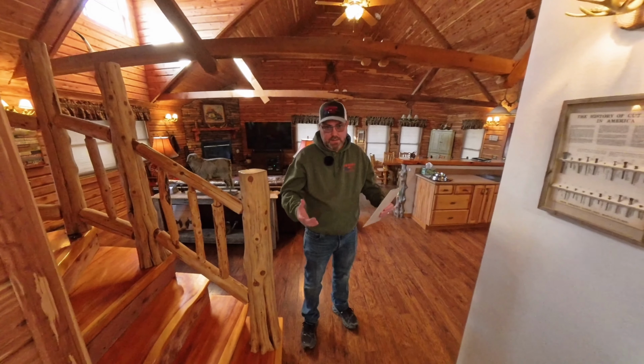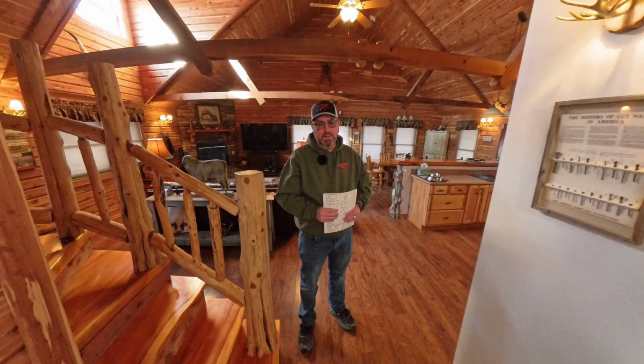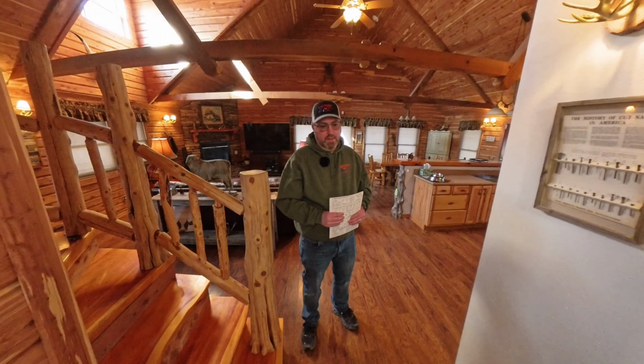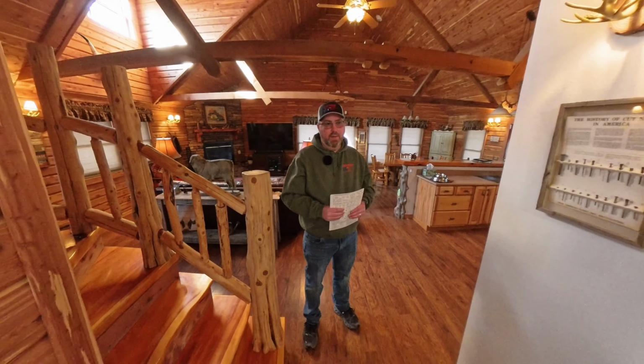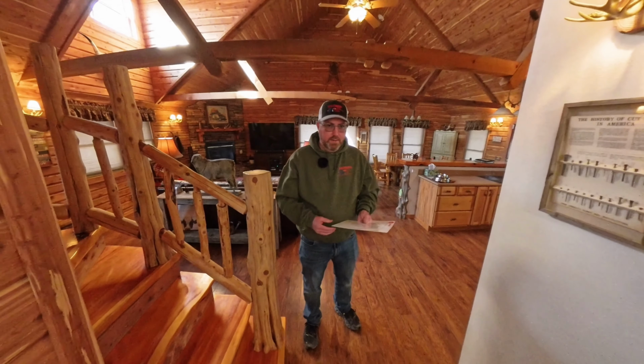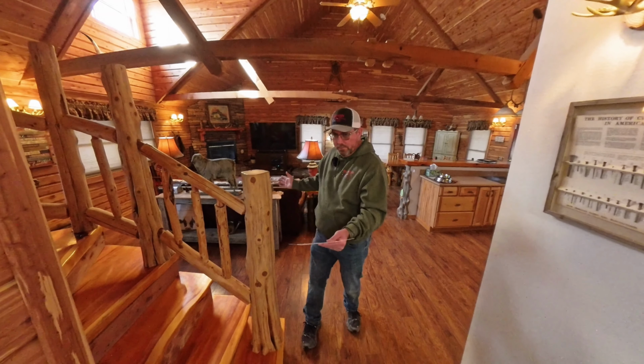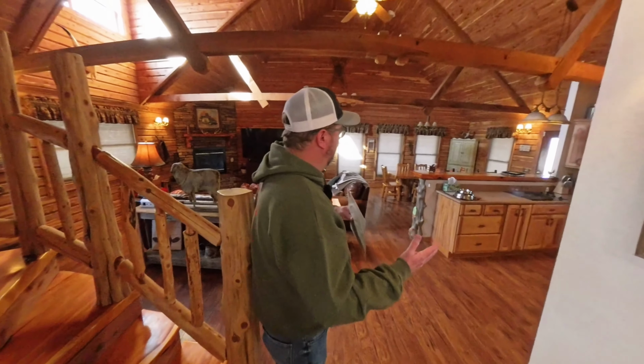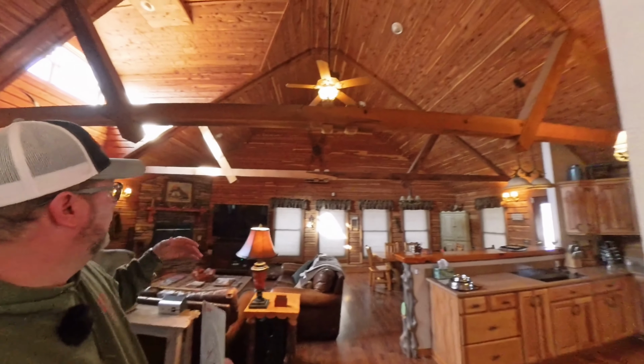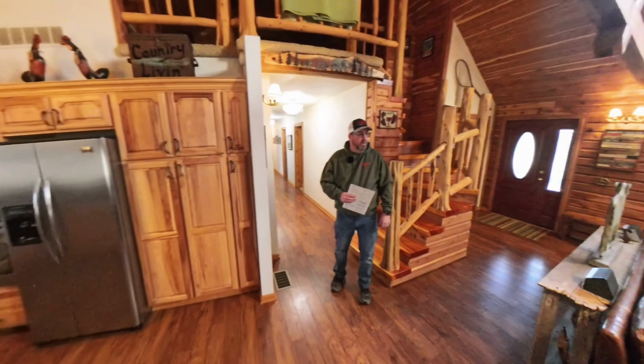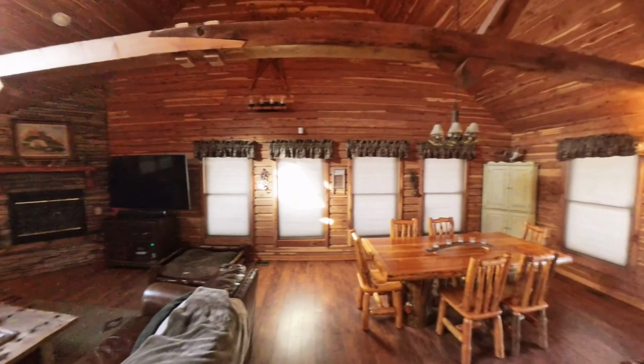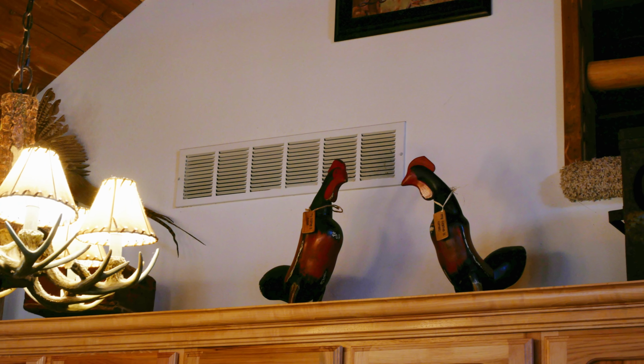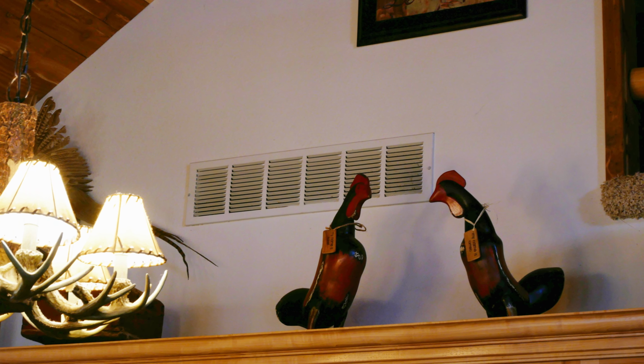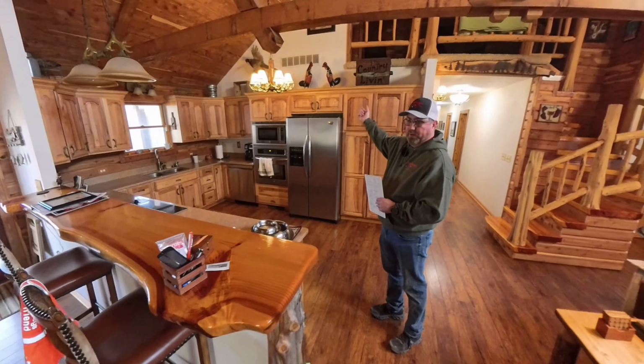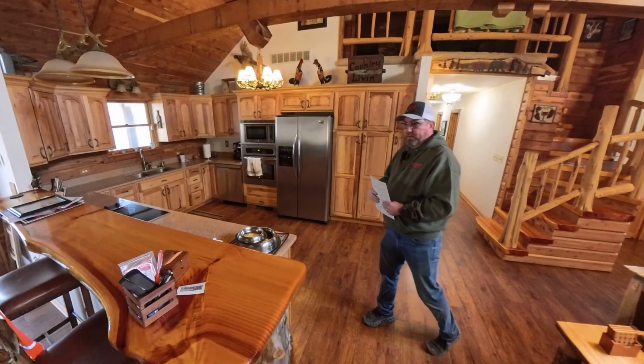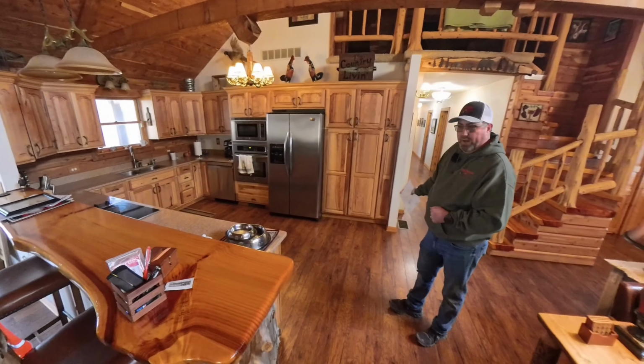system. Producing the CFM that we need, period, for the system to operate correctly is going to give you not only balanced airflow, but if you can't bring back what the unit needs, you're not going to put out what it can produce. This was the concern. These big tall ceilings, this nice big open room, there were not enough supply registers. Plus, when we talk about return, up here on the wall is the only return register for this big open area. So that's why we chose to put the return in the floor out in this area.